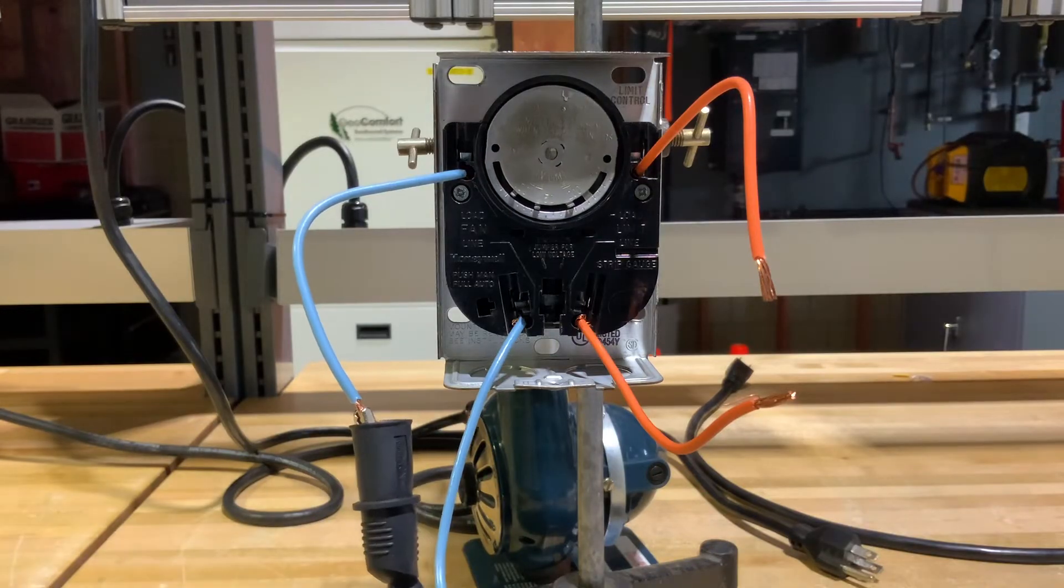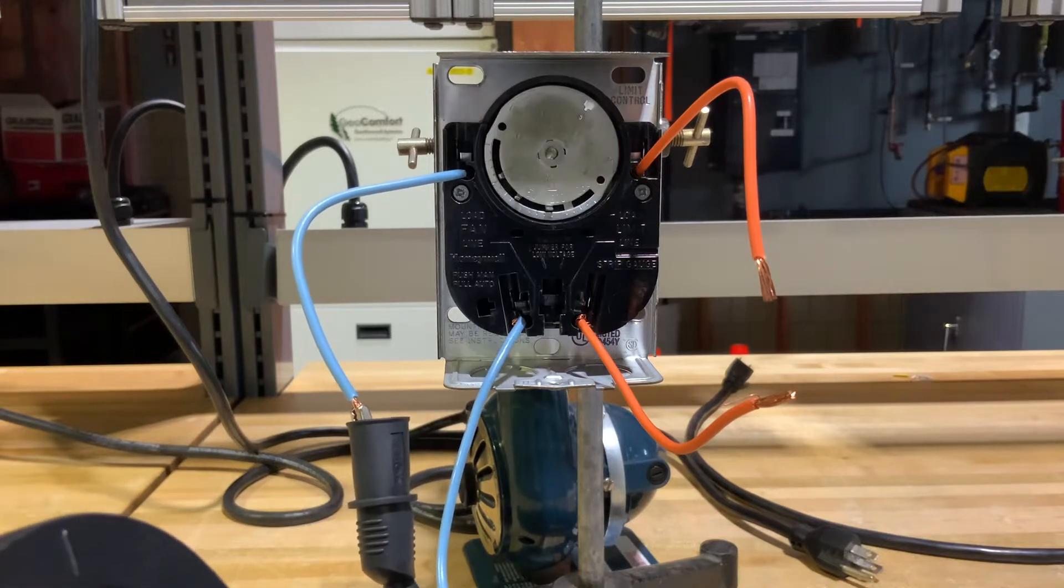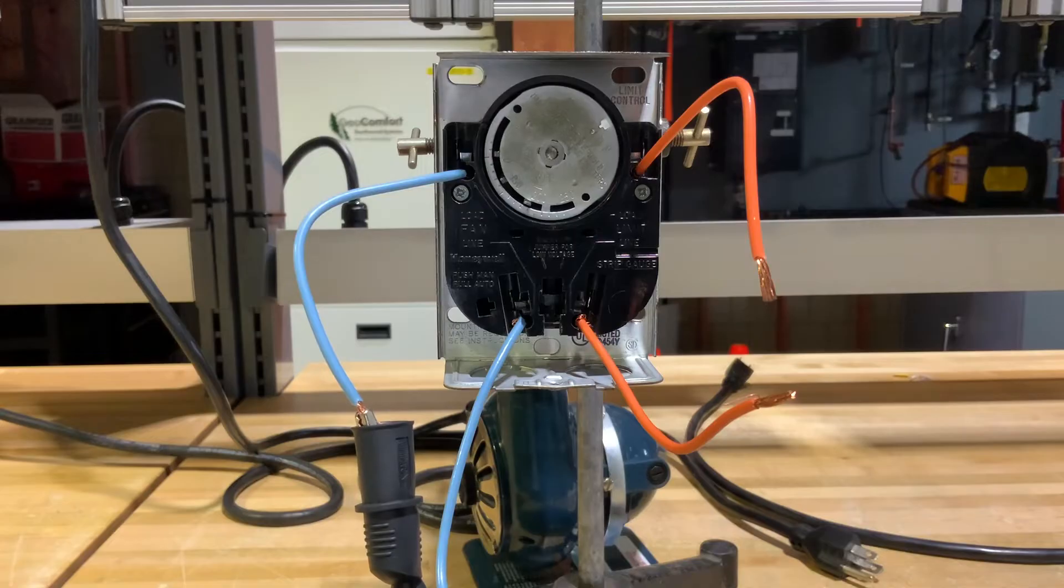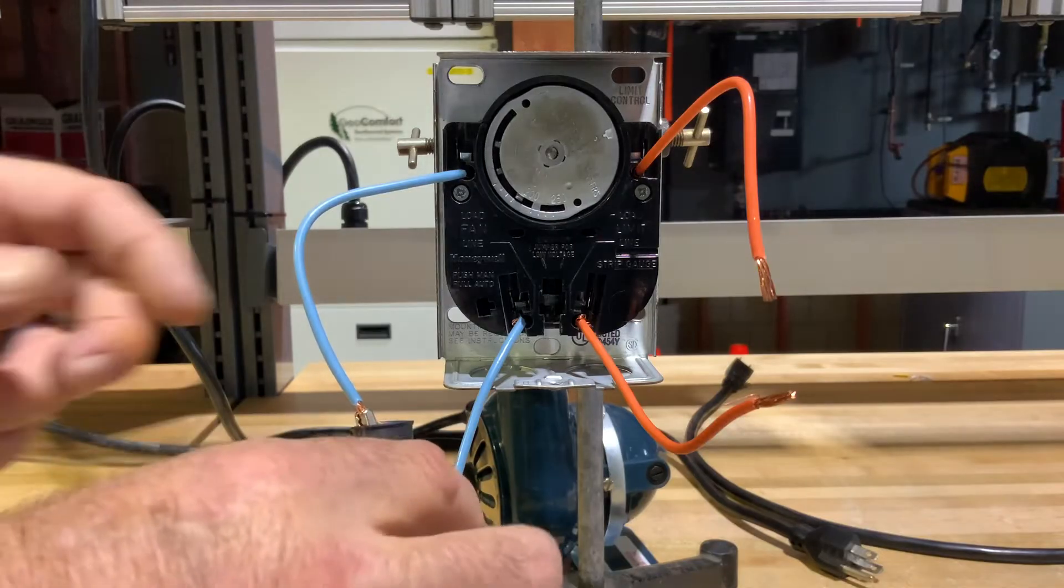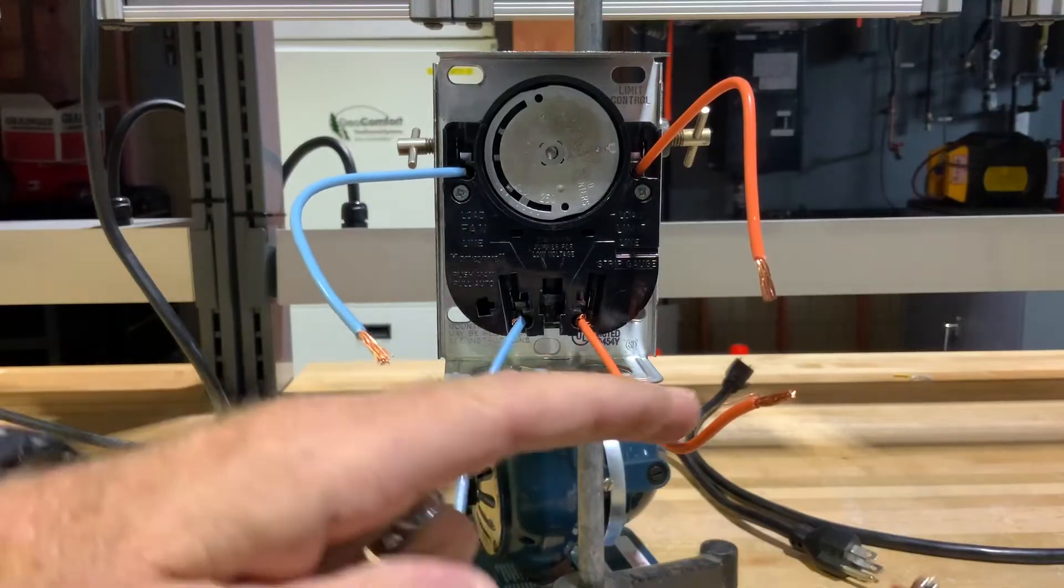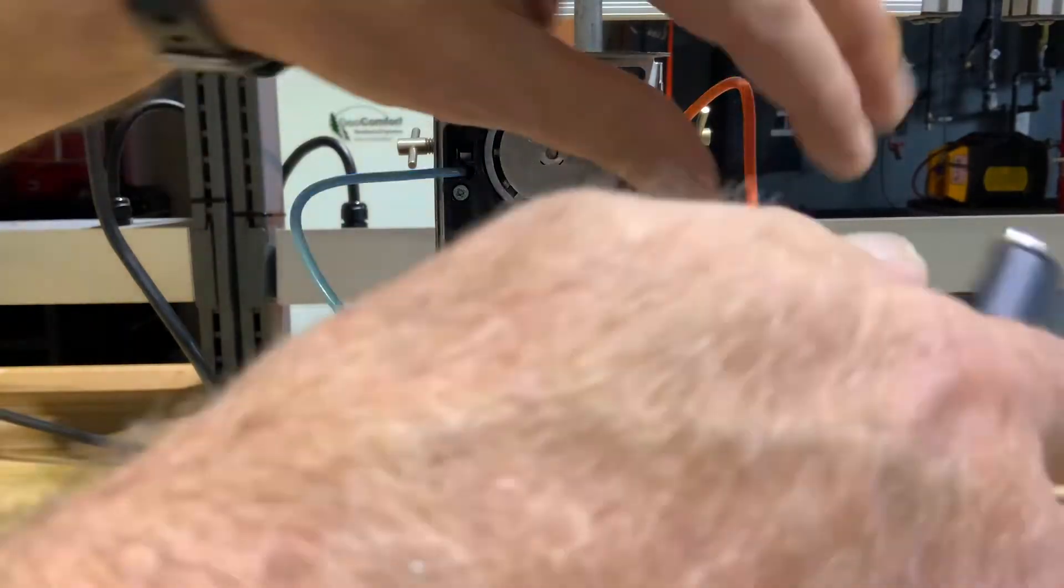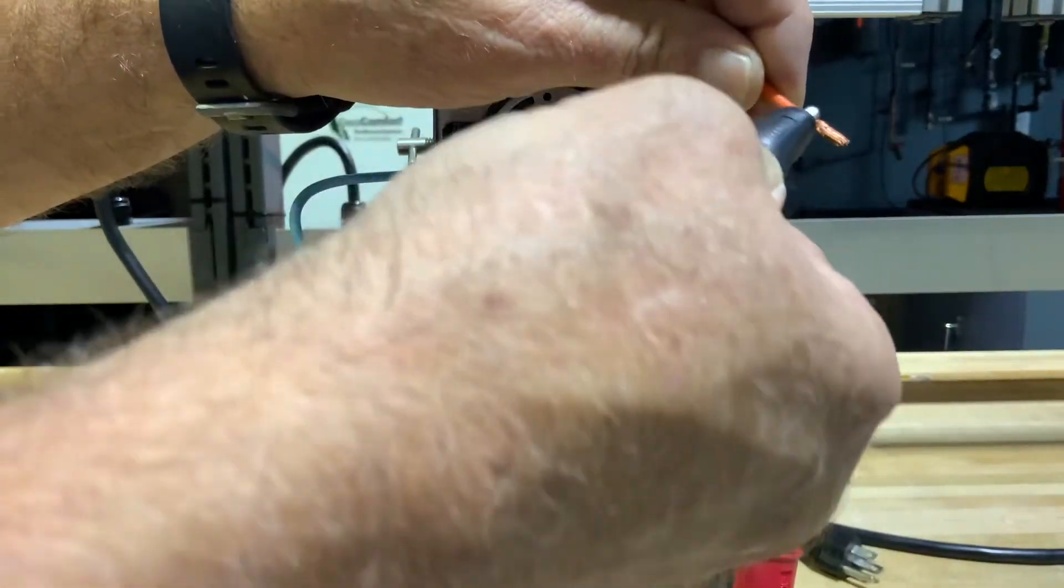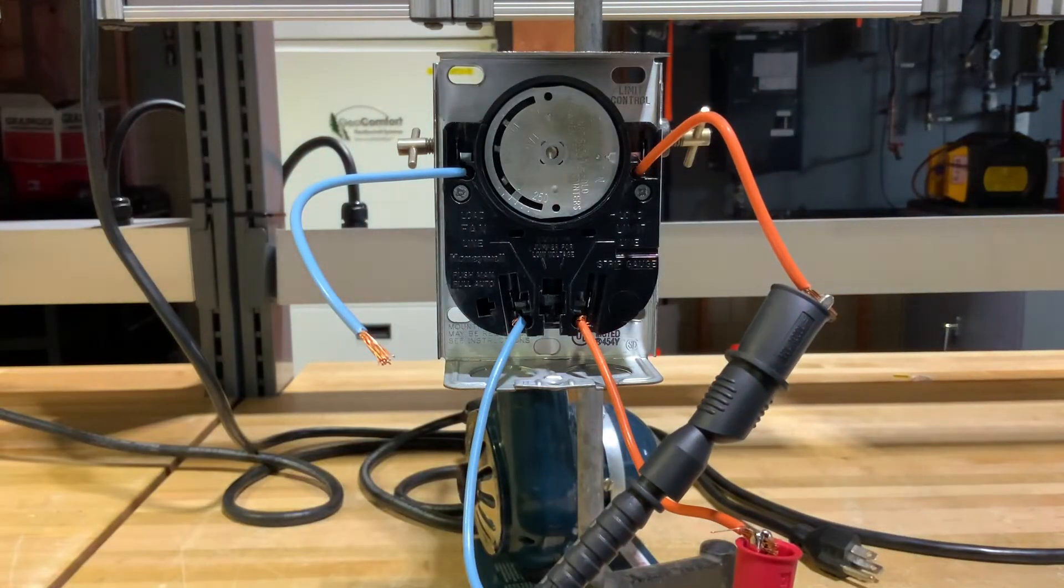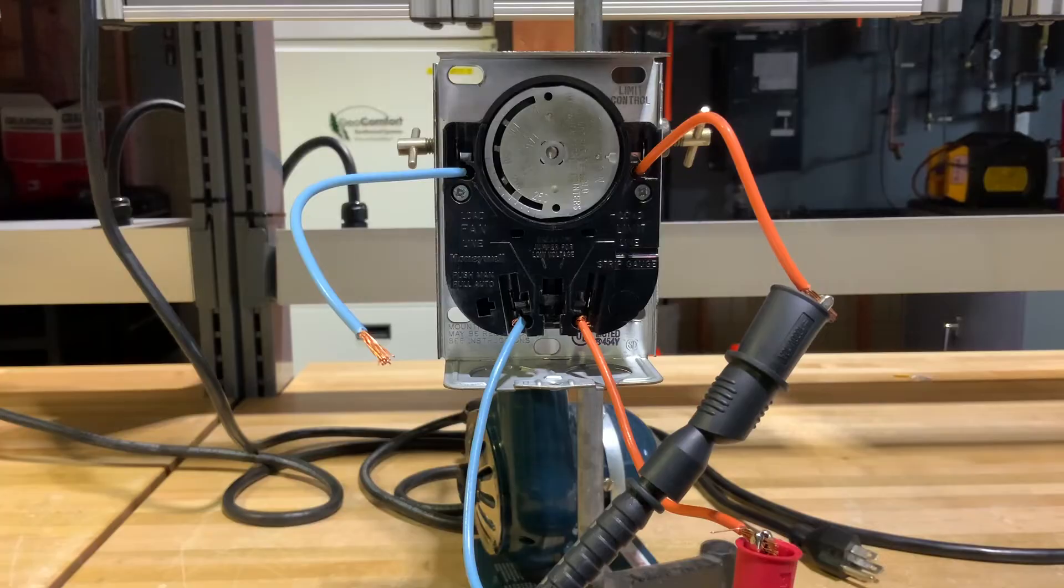Now we've hit that temperature and our meter is going. Now we've hit the other temperature where we got too hot. If I check that high limit, I have no continuity through that. That shuts off all power to the primary control - that's going to shut down our burners and our pumps and everything.